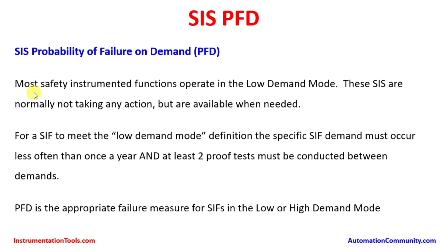Most safety instrumented functions operate in low demand mode. Generally, process plants operate on a low demand mode as far as the SIS is concerned. These SIS are normally not taking any action but are available when needed. The safety instrumented system is always active but components are not moving every time. They are like a passive system and they operate whenever there is any demand or hazardous event happening in the plant. At that time, the sensor does sensing of the process parameter measurement, the logic solver makes logical calculations and provides an output to the safety instrument system — for example, for valves — and then operates. They are always available but keep silent.